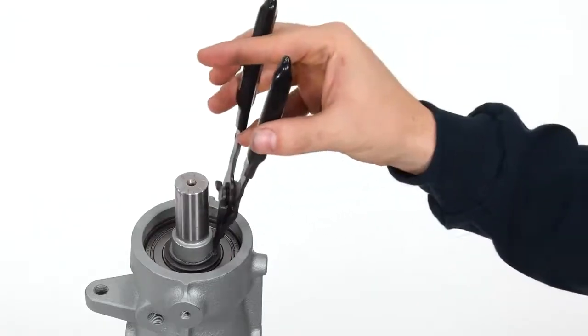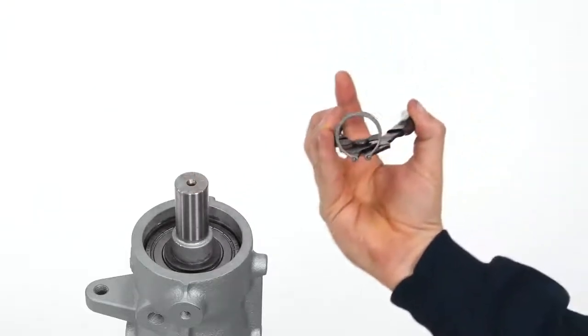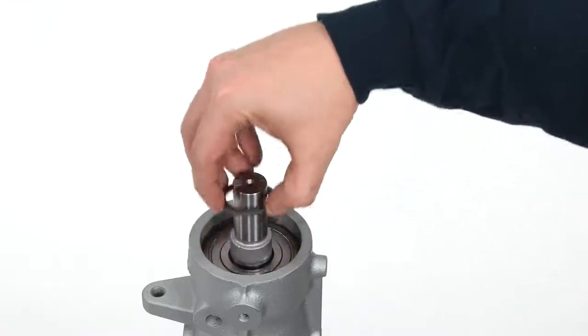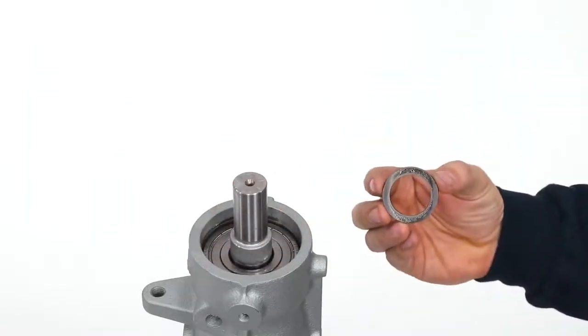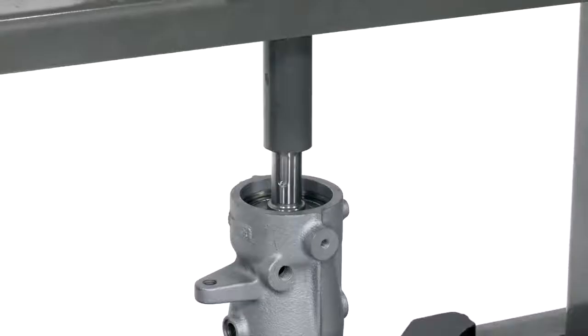Next, remove the inner snap ring, followed by the inner spacer. Using a hydraulic press, press the shaft out of the bearing frame towards the impeller end.